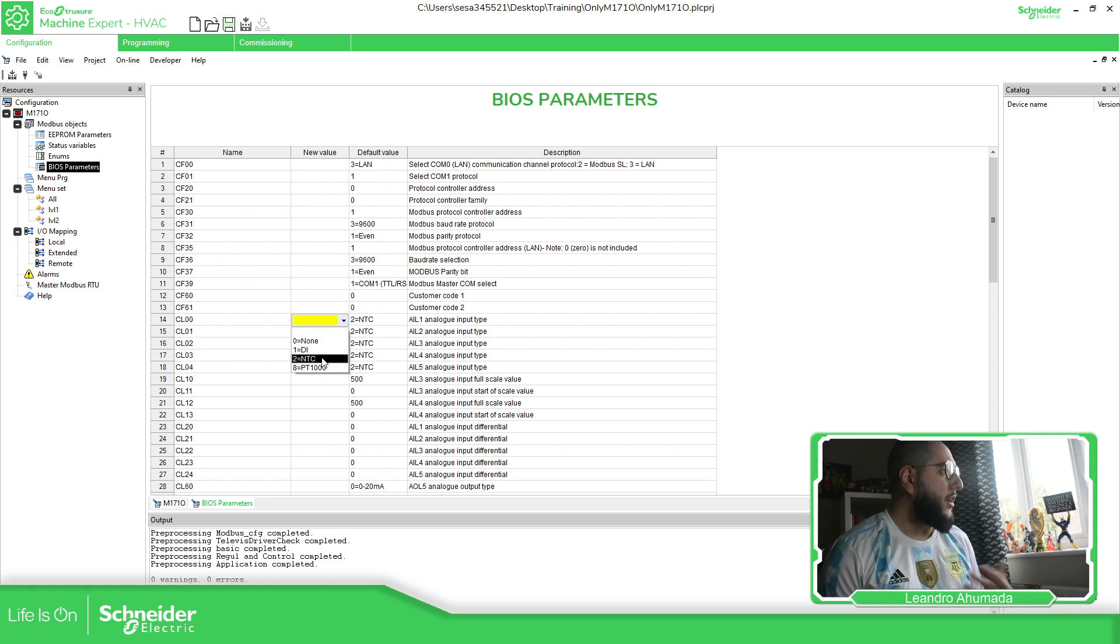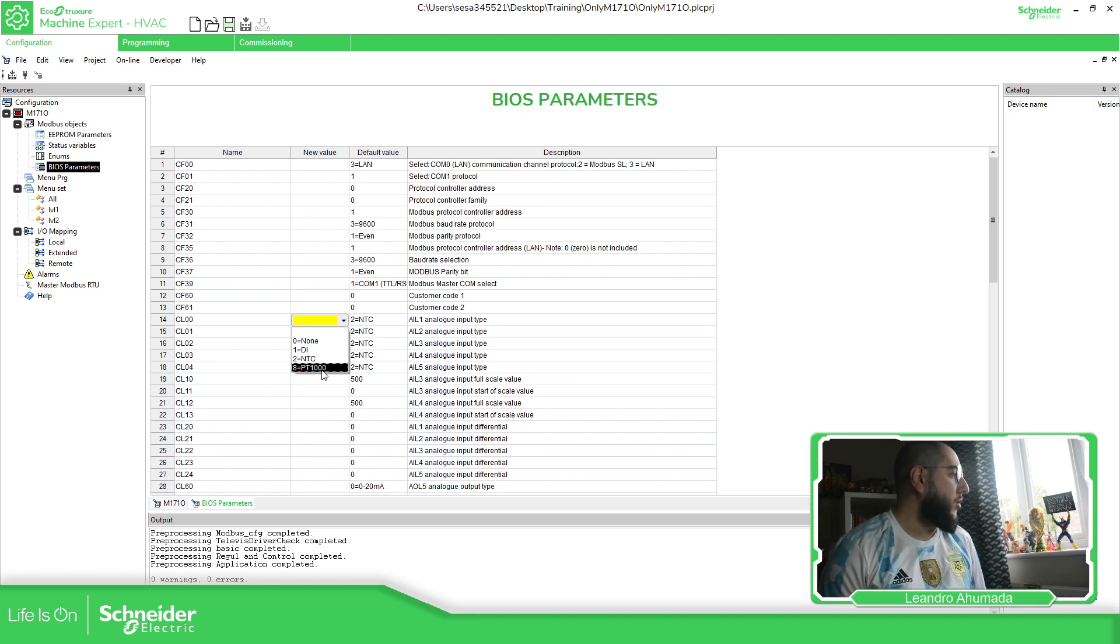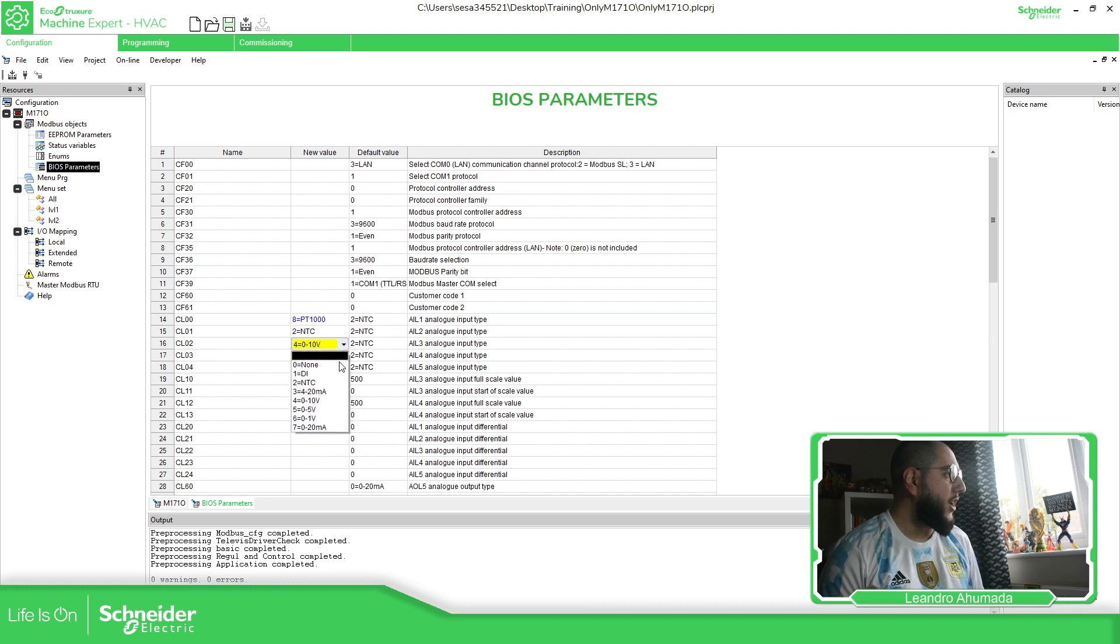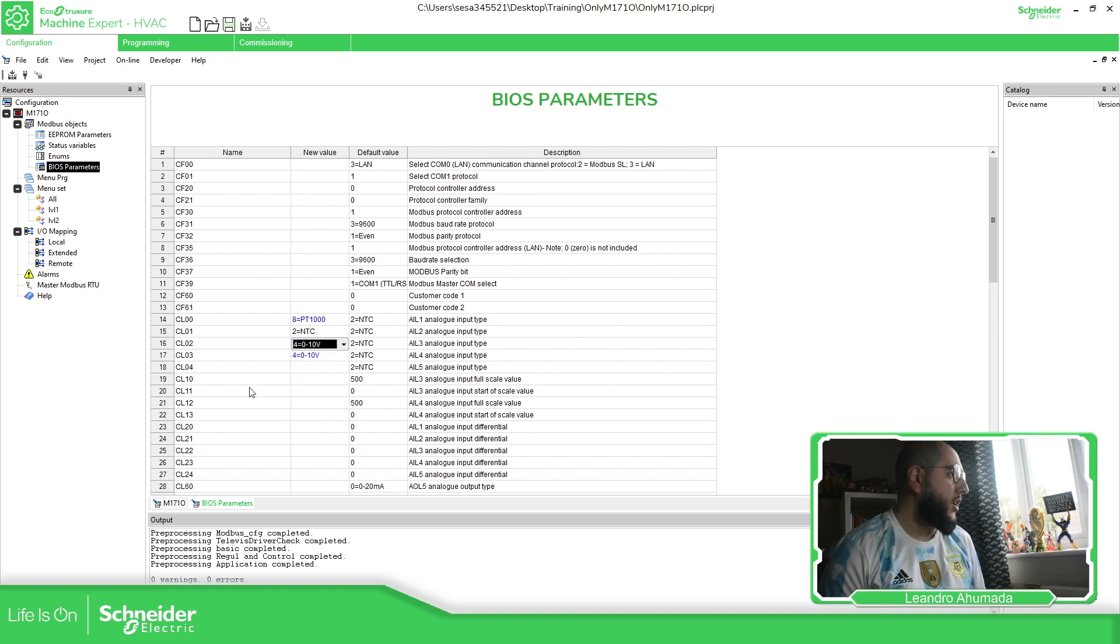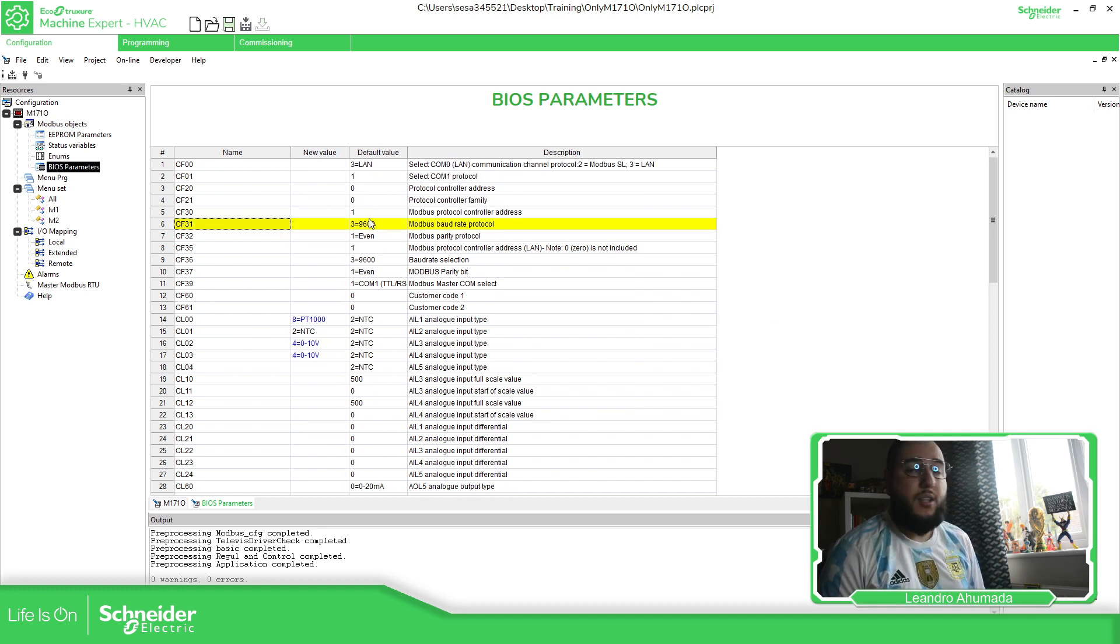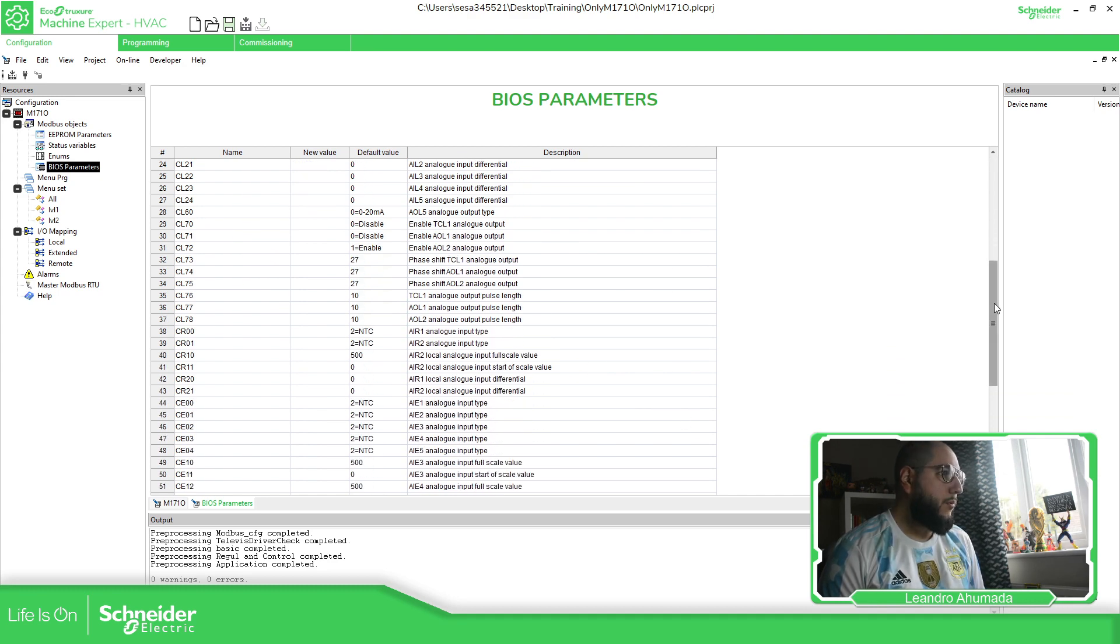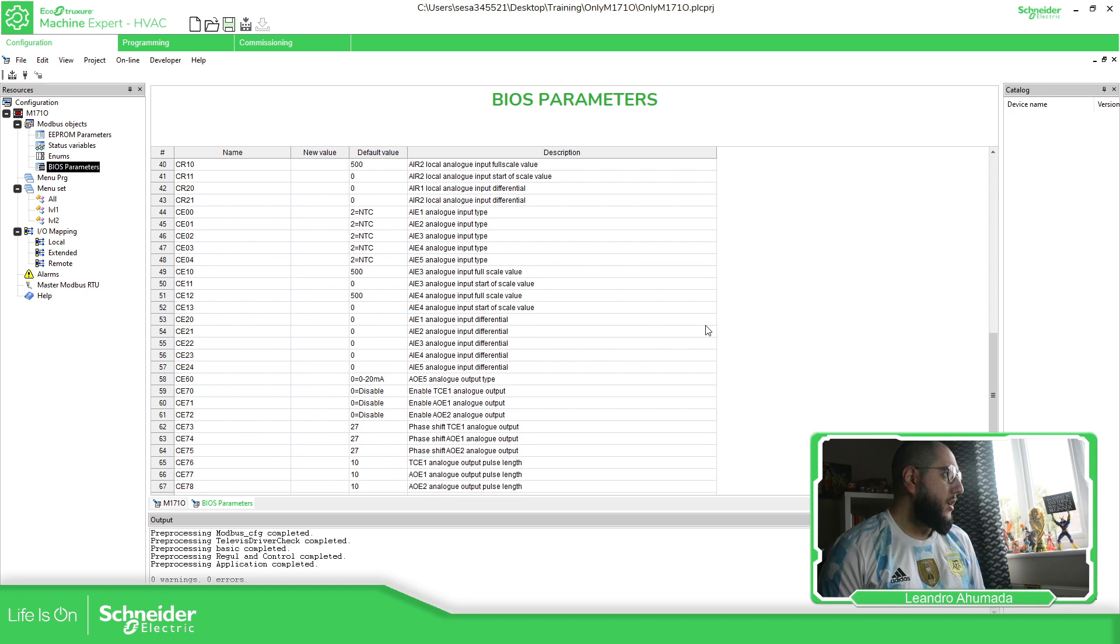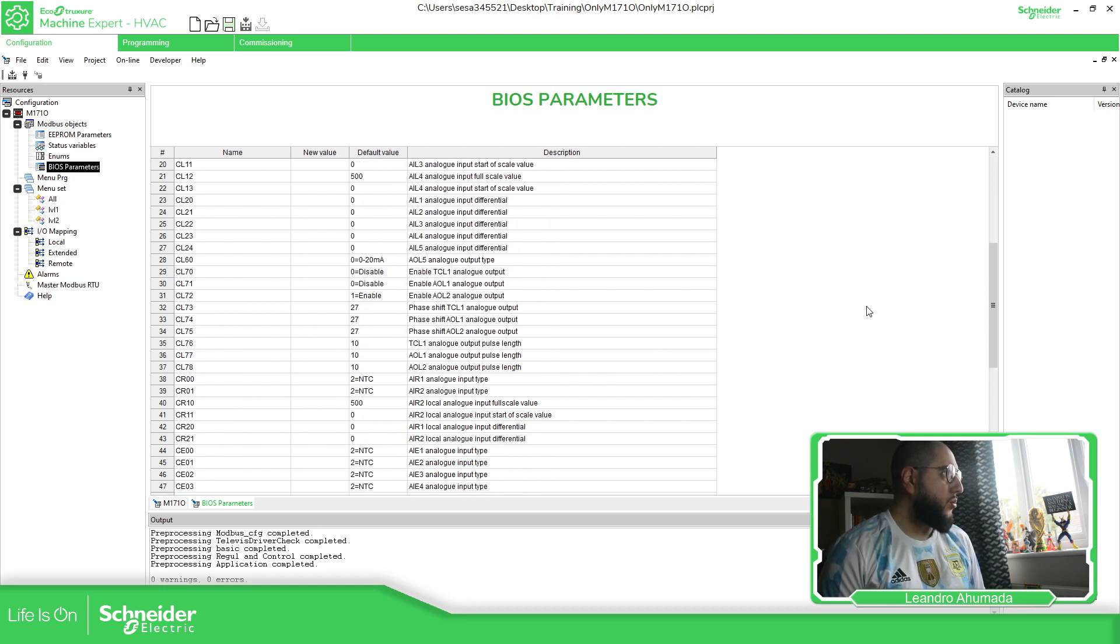We're going to cover that later, but here, depending on the controller, you have different settings for the analog inputs. So in this case, I'm going to say PT1000 and this one NTC, you can make the variation, but in this case, for example, analog input three and four, we have more configurations. So it's good to check on here what you can do. Then you have also the configuration for the Modbus settings. There is a few more things here, but everything is about the passwords that you can set.